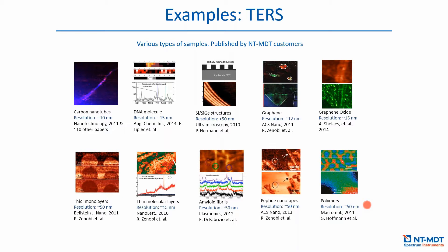Remember several things that are important for TERS: the system has to be very stable because TERS occurs only inside the tightly focused laser beam with diameter of about 300–400 nanometers — so the probe must stay inside that laser. The second critical aspect is the TERS probe itself. Our company makes TERS tips, but you can also make them yourself, and we can guide you with publications on how other researchers prepare such tips. Of course, sample preparation is also important.